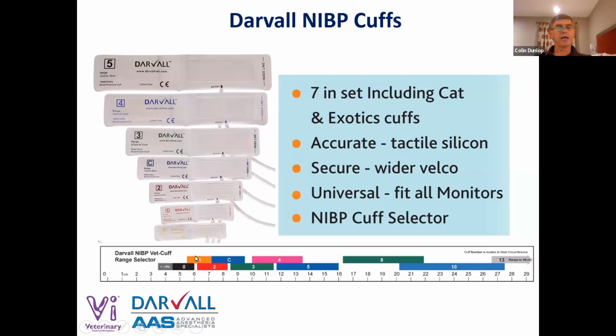The other thing you can see here is that the cuffs should overlap. So here's a human: 1, 2, 3, 4, 5. There's no overlap here between a 2 and a 3. If you measure a cat, the ideal circumference of a cat's limb, forelimb or hind limb above the hock, is about 8.4 centimeters. So the problem with cats is they're too big for a size 2 and too small for a size 3. So we make a specific cuff to fit cats. And it's the width of the cuff that matters, not the length.